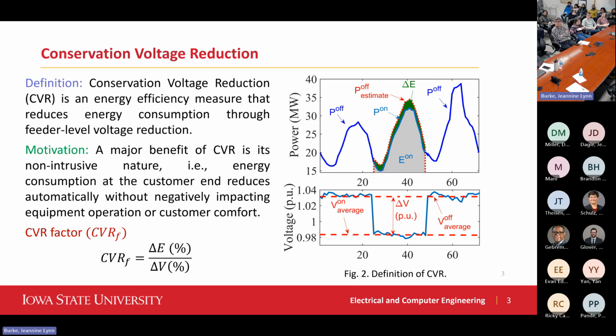So it's pretty simple. Basically, the utility just reduces the voltage at the feeder head using their voltage LTC, load tap changer. That reduces the voltage a little bit, but still within the ANSI standard. It's just a lower range of the ANSI standard. So it won't affect anything, but you reduce the voltage.